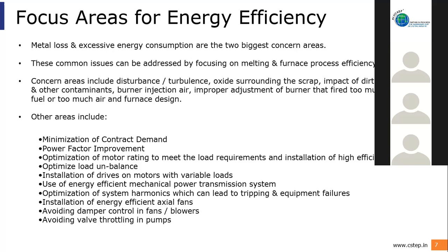Optimization of motor rating to meet the load requirements, and installation of high efficiency motors. As a thumb rule in the industry, if the motor is loaded above 50% of its rated capacity, it's fine and there is no need to change it. But if the loading is less than 50%, and there is a variable load, whether the motor is driving a pump, a blower or any other equipment, we need to look into it. There is scope for optimization. Then, optimization of the load unbalance. In MSME units, we have often found a load unbalance in the system. The three phases are carrying variable loads, which can lead to higher losses in the system.